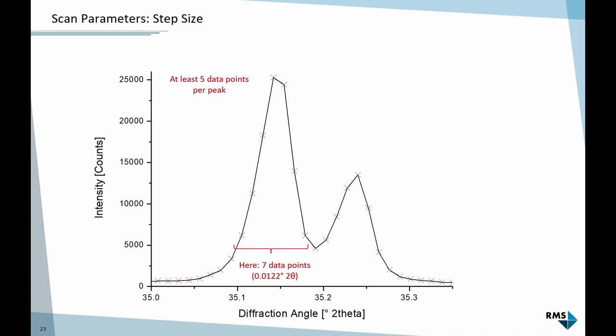You can also oversample your dataset - you don't need super fine description of your sharpest peaks. It just takes much longer but doesn't really help. The dataset will be larger, scan time longer, and data processing slower. At least five, seven points to describe the sharpest peaks in your sample is sufficient. Typically this value for lab instruments is somewhere in the range of 0.01 to 0.02 degrees two-theta.